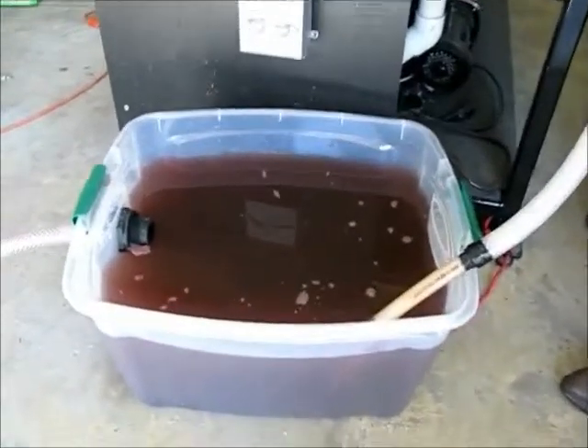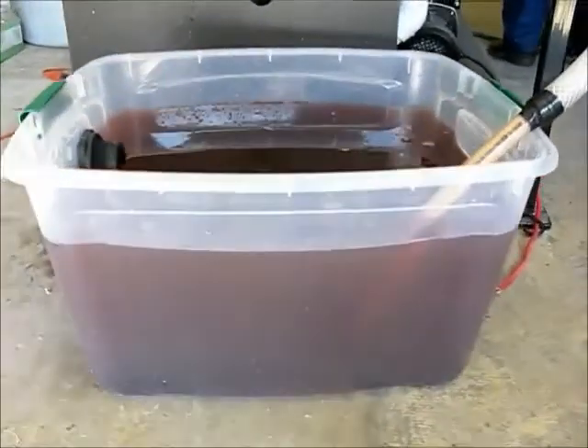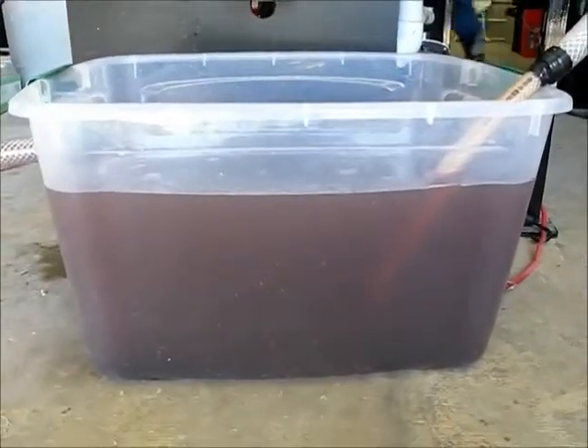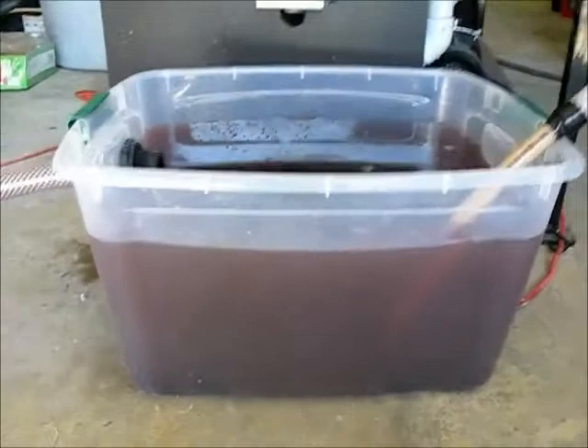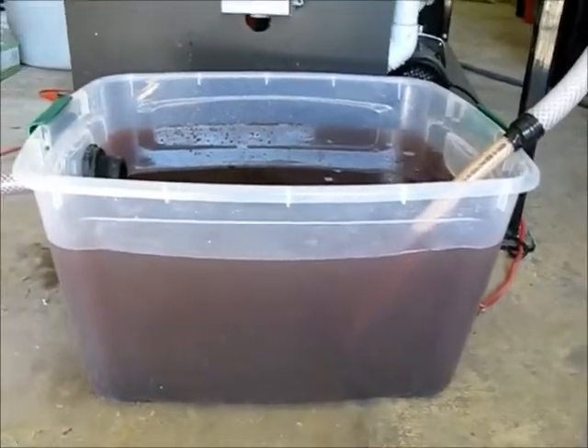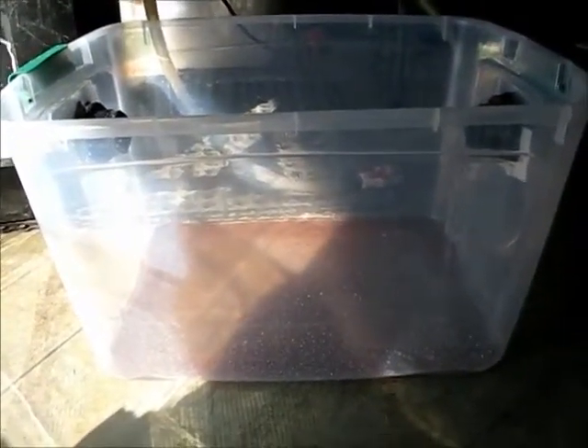We've now treated 20 gallons of the dye. The floc is developing and there's more floc on the bottom than on the top. It still needs a little more time because the floc is so fragile, and what we're doing here is just gently overflowing into a second container — this would be the equivalent of a weir tank. A simple divider between a tank would achieve the same effect, and what will end up here is much cleaner water and a lot less floc on the bottom.